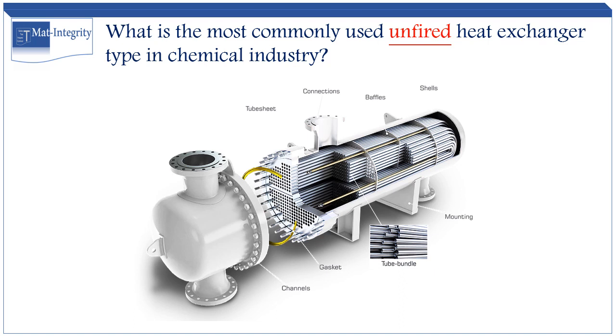The second component is a large number of tubes bent to a U-shape and assembled together in a specific pattern, then welded to a rounded shape plate. This plate is called the tube sheet, and the complete assembly is known as the U-tube bundle.